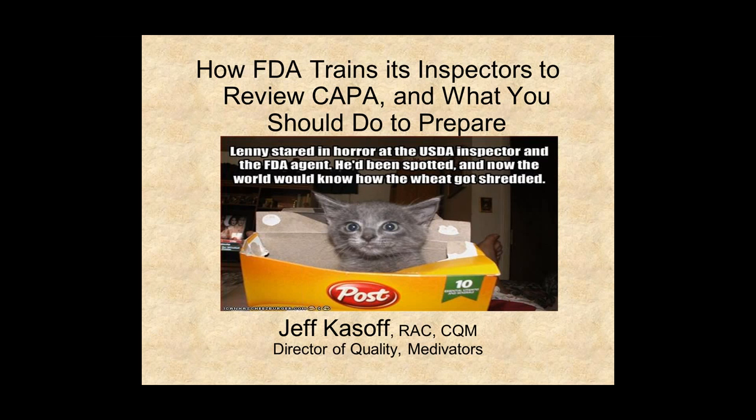When you deal with CAPA, a lot of us have different varying CAPA systems at our facilities, and it's difficult to anticipate what the FDA inspector is going to look for, whether they'll think your system meets the regulatory requirements. However, what you'll see in this webinar is the areas that the inspector will look at, the questions they'll ask, what samples they'll take, and along with that, some recommendations that, based on my years of experience at several different facilities during a couple of dozen FDA inspections, the inspectors have appreciated.